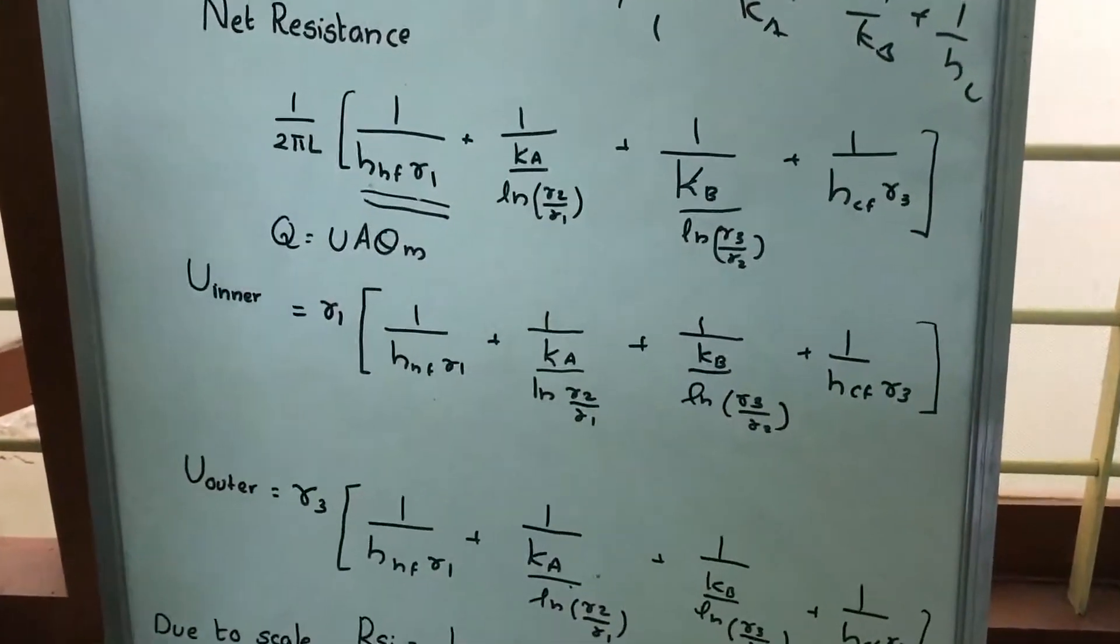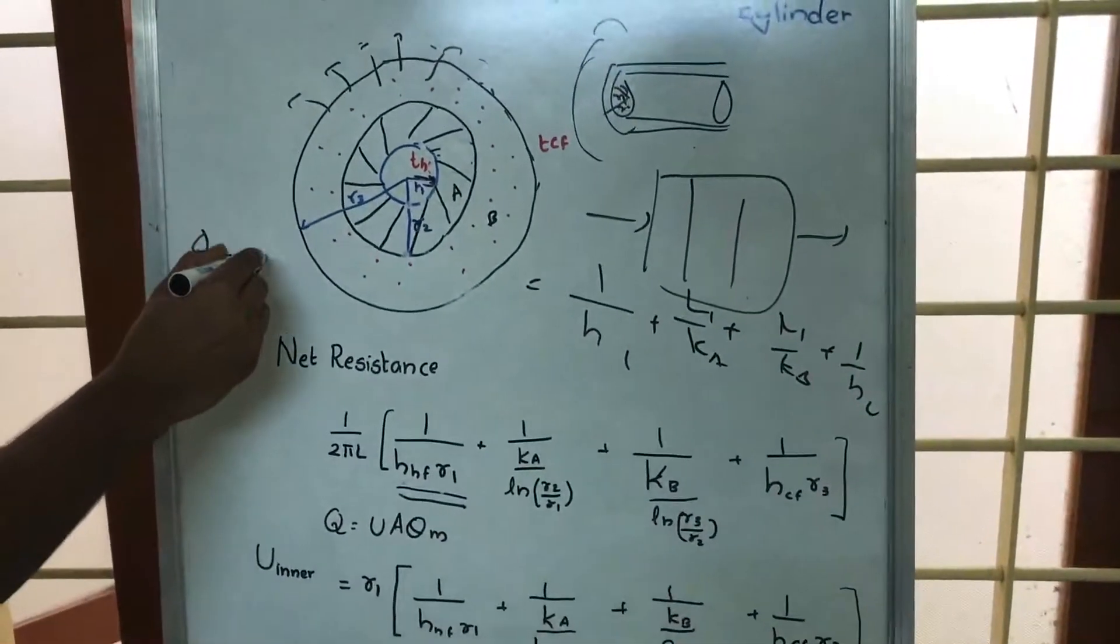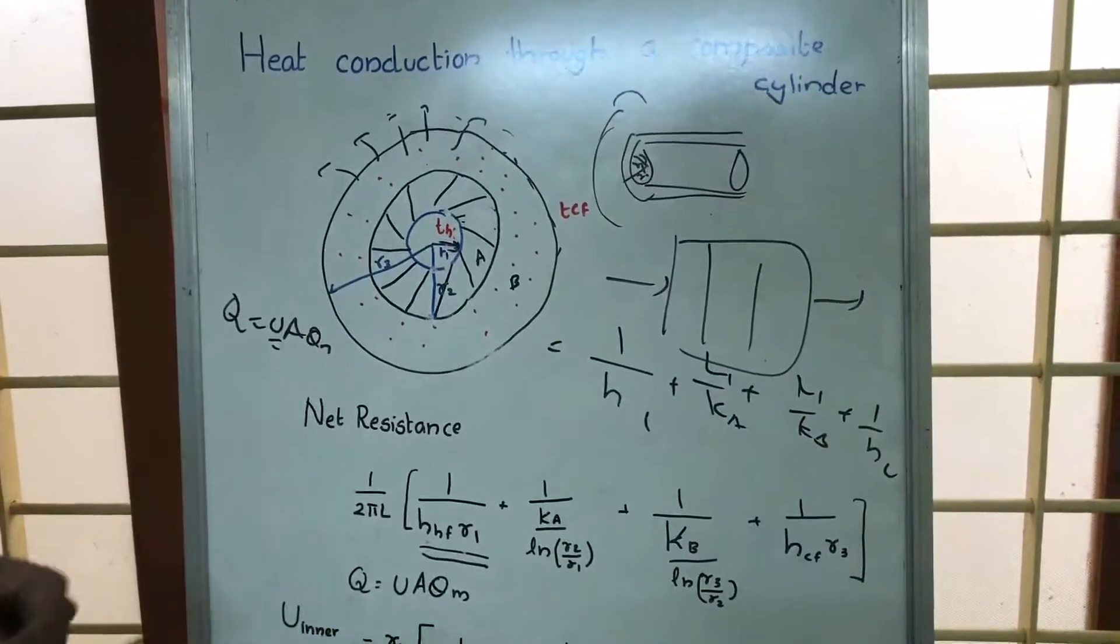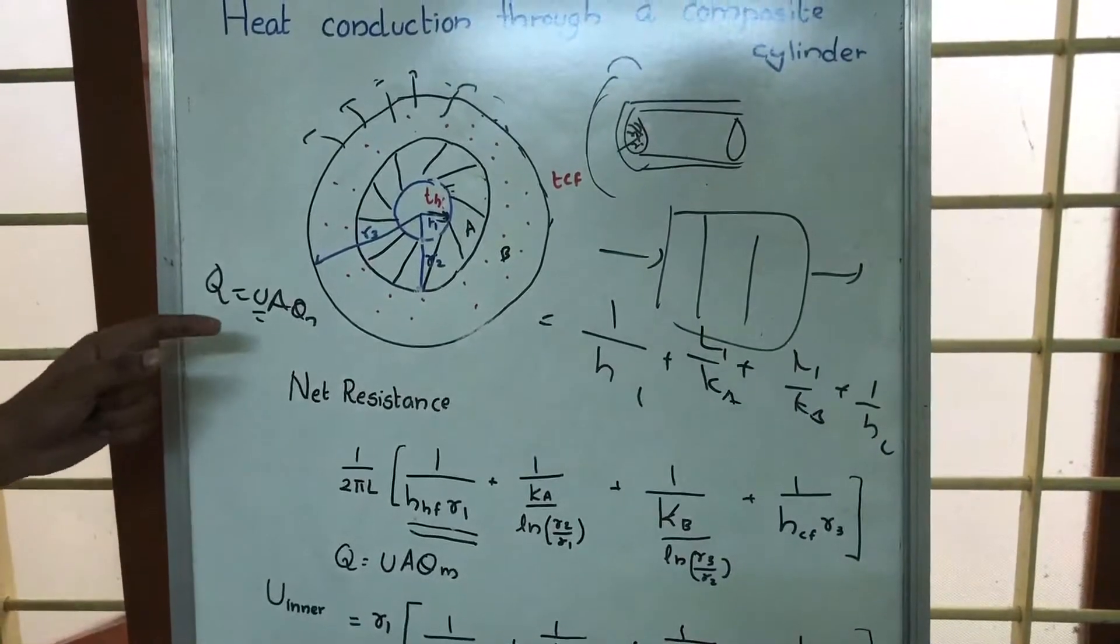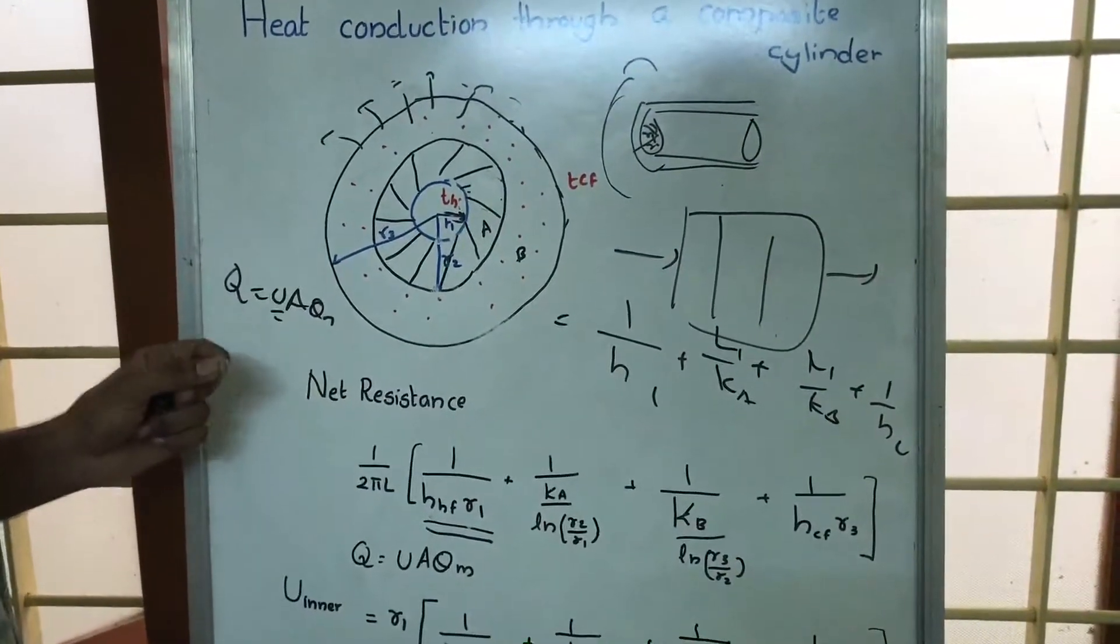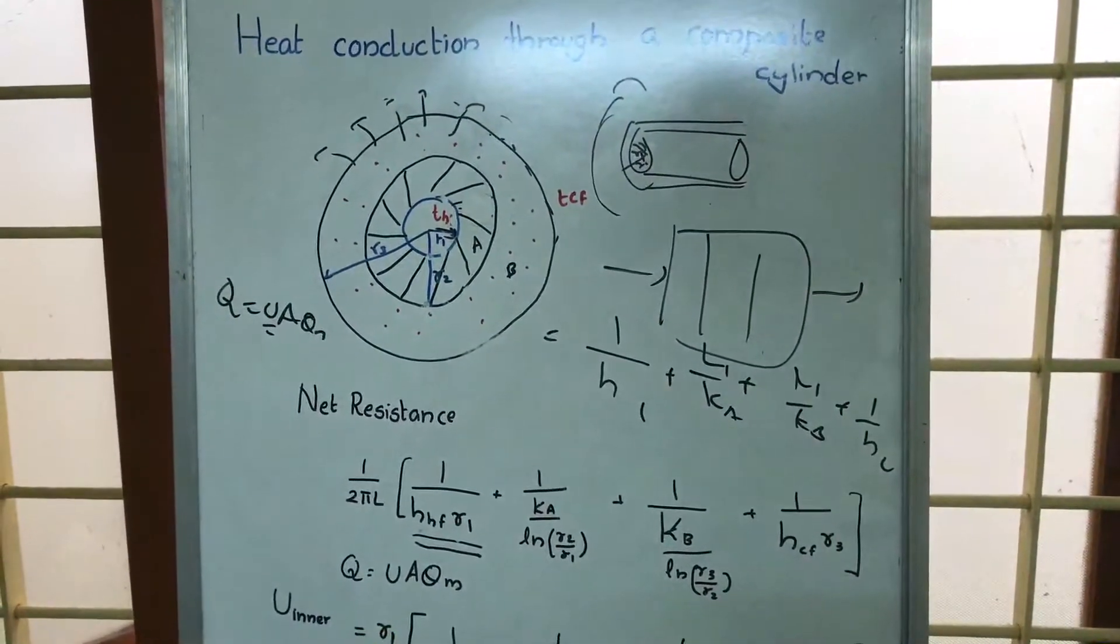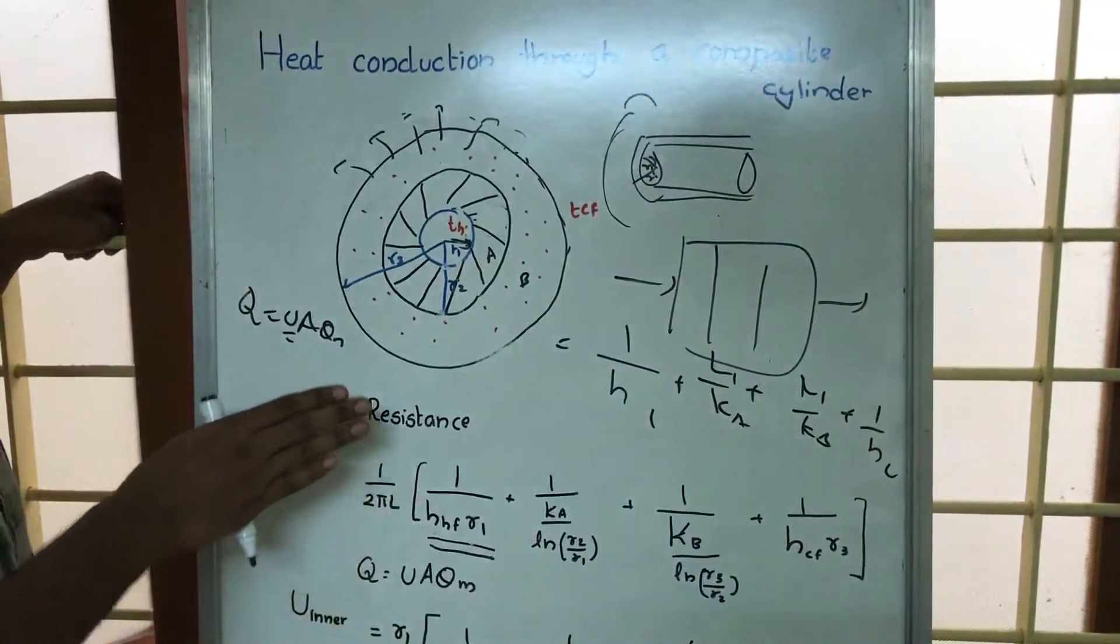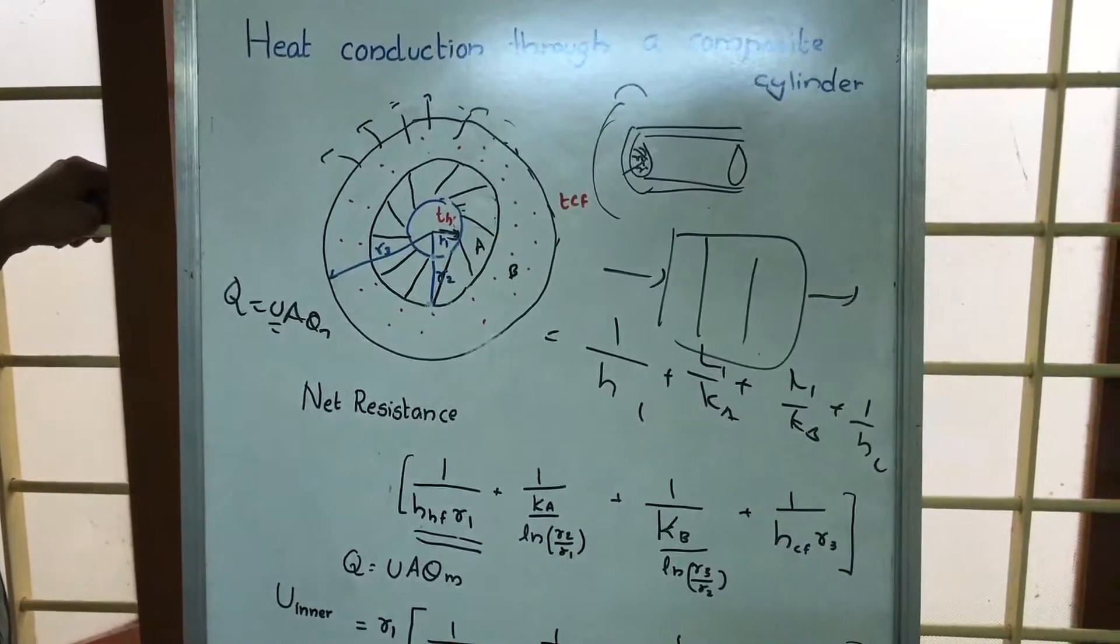Now if you have to find this, Q equals U A θM, where U is the overall heat transfer coefficient. We can find U by either considering the inner surface or the outer surface. From this net resistance, in order to get U, we should remove the 1 by 2πL term.